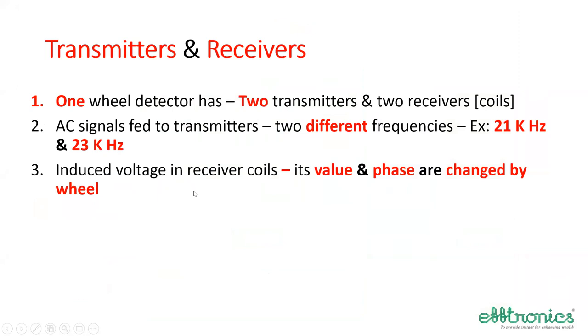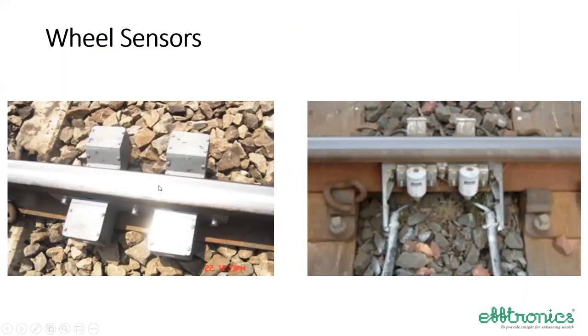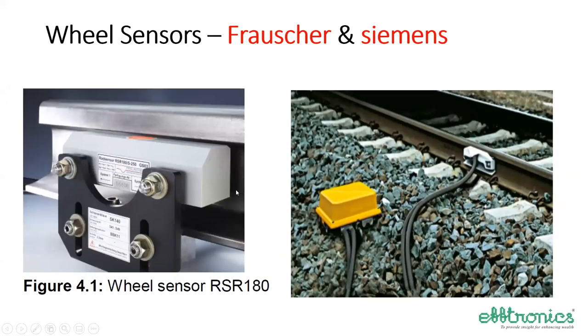So one wheel detector has two transmitters and two receiver coils. Different frequencies are fed to these. One is given 21 kilohertz and the other one is 23 kilohertz. The induced voltage in the receiver coils, its value and phase both are changed by the wheel. So wheel sensors look like this. You can see these are different types of wheel sensors, different makes. Frauscher and Siemens ones look like this.